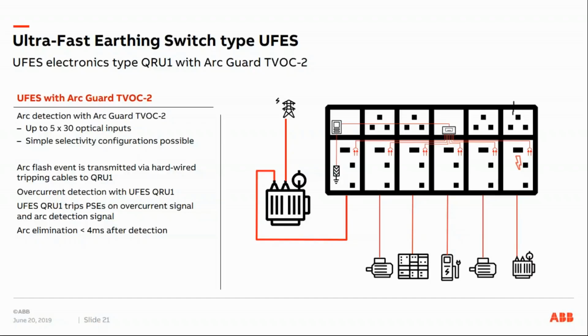Here you would have in the first panel the primary switching element together with the UFES control unit, and the TVOC in one of the other panels with its respective optical inputs leading to the different neighbor panels. The arc flash event is transmitted via hardwire tripping cables to the QRU1, and the overcurrent detection is done by the control unit itself. And as previously mentioned, the control unit trips the primary switching elements after it detects an overcurrent and an arc, or it receives an arc detection signal. The arc elimination is, as mentioned, in less than 4 milliseconds after the detection.